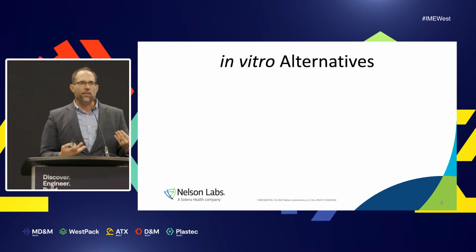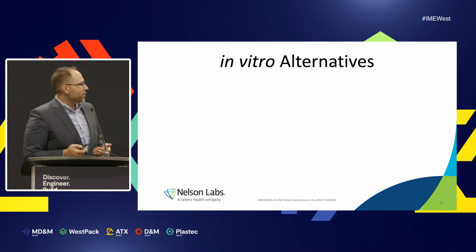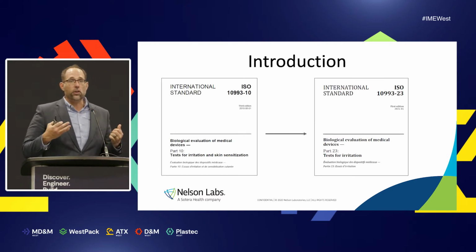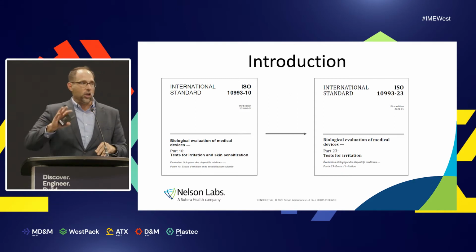Okay, one of my favorite things to talk about is this new 10993-23, okay? The new -23 was introduced just recently this year. And for those of you who don't know, we took 10993-10, which is sensitization and irritation, and we broke them apart. So we kept sensitization in -10, and we took irritation into -23.